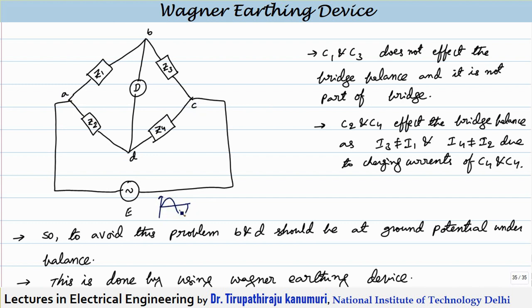That means we can tell that neither point C nor point A is at the ground potential. Because this is not at the ground potential, capacitance will be formed between this potential and the earth. Capacitance is formed between two conductors placed at different potential. Ground acts as one conductor and this point is another plate, because both are at different potential. So capacitance will be formed between them — one capacitance will be formed between this point and the nearby ground point. This capacitance I am naming as C1.